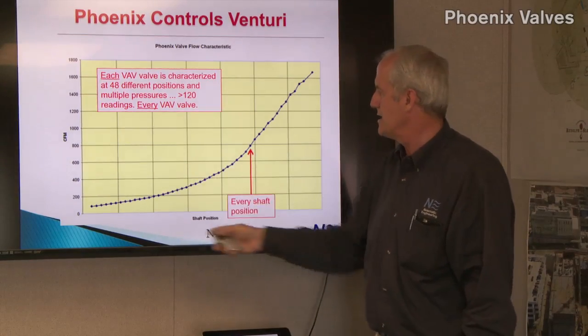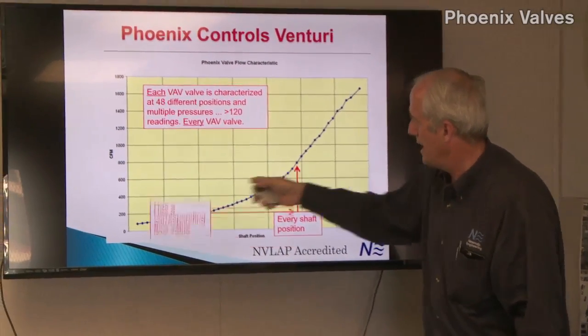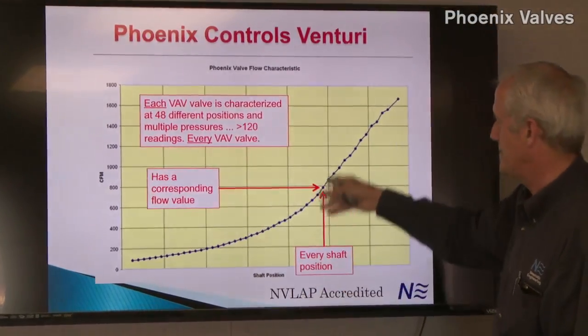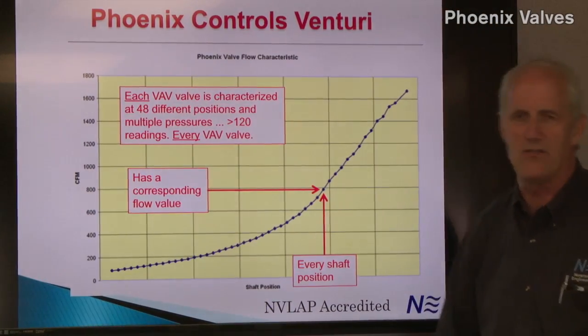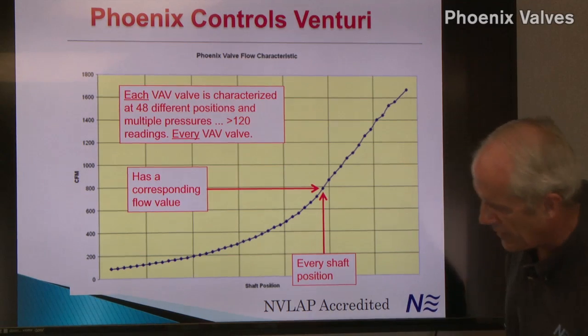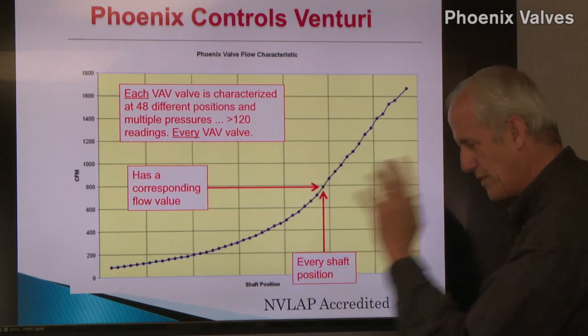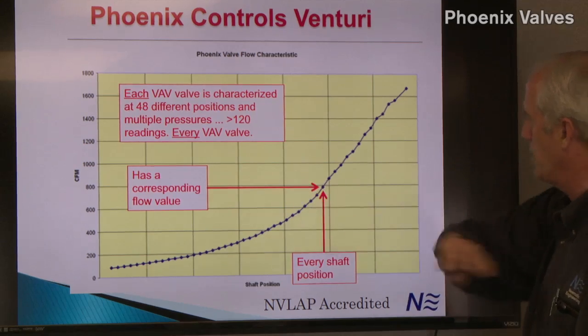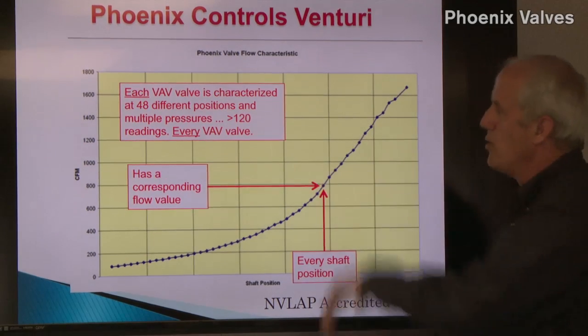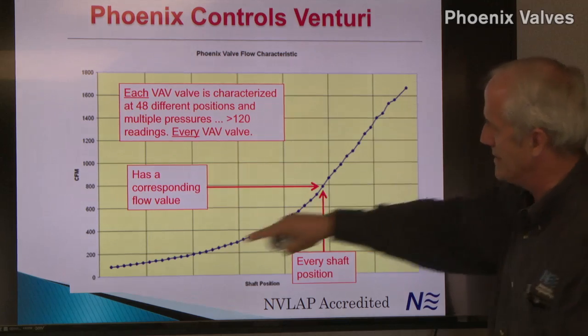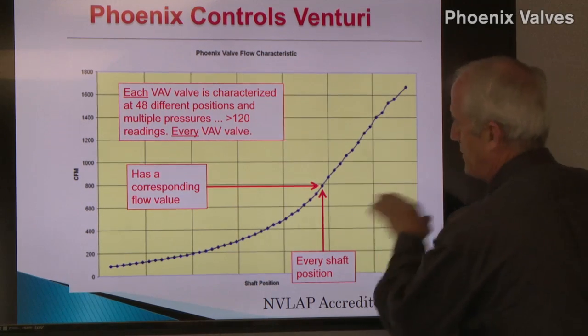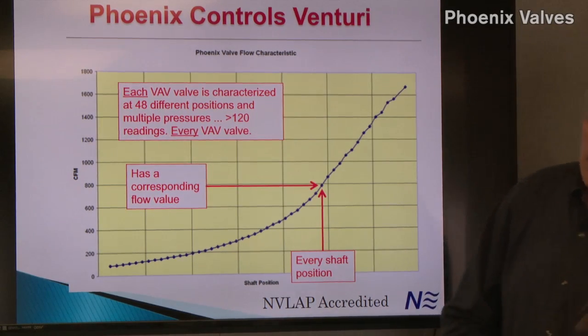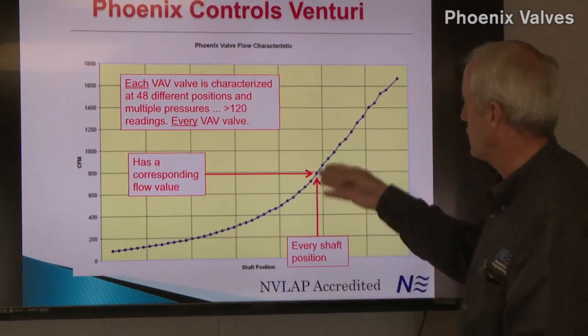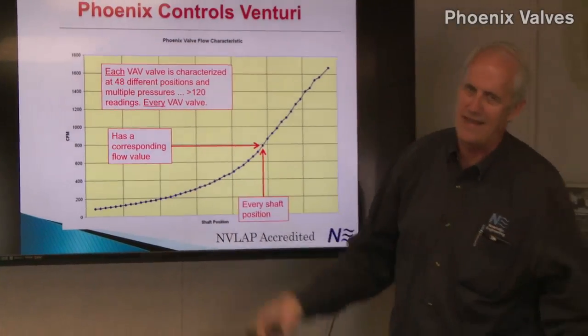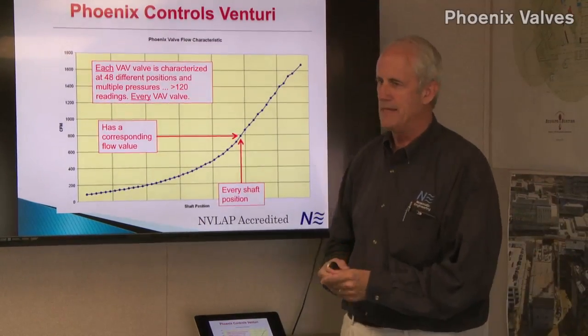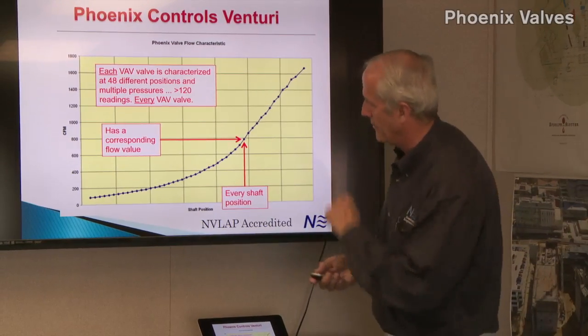So for a given shaft position, you have the corresponding flow. This shaft position would give you 793 CFM. So when we move our valve to a position, we know precisely where that position is through a rotary potentiometer, and that will give you that flow. And we've characterized the valve at the factory, so we know that position is that flow. The only reason that position wouldn't give you that flow is if your fan is off or underperforming, and we have a way to correct for that on this job as well.